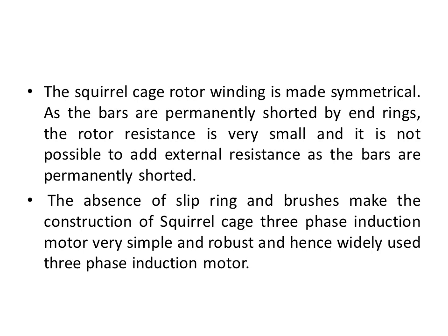The squirrel cage rotor winding is made symmetrical as the bars are permanently shorted by end rings. The rotor resistance is very small, and it is not possible to add external resistance as the bars are permanently shorted. If you want to increase the load or add external resistance, it is not possible in a squirrel cage rotor. But 90% of induction motors are made based on the squirrel cage rotor.